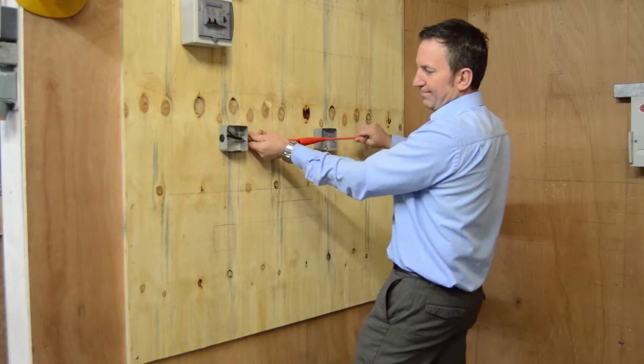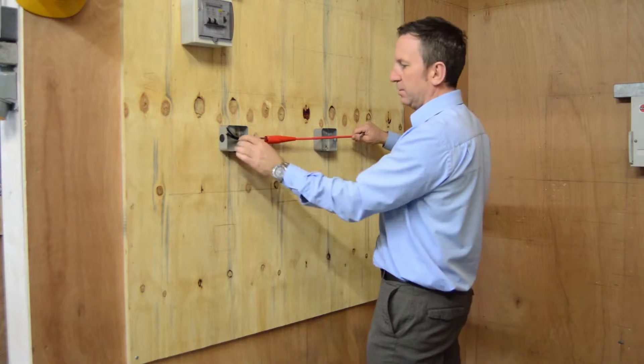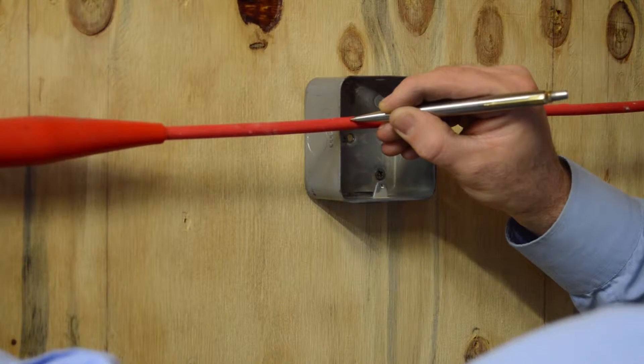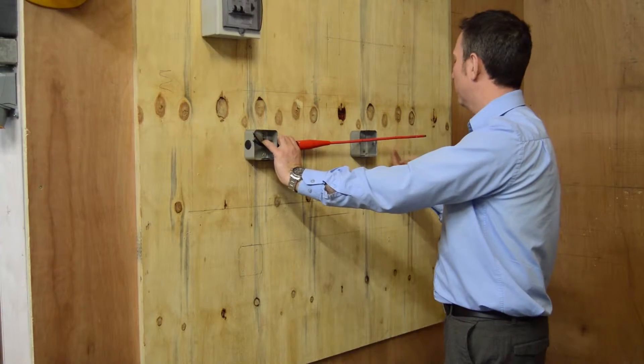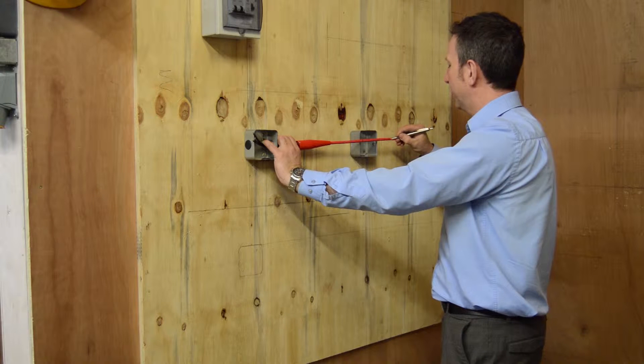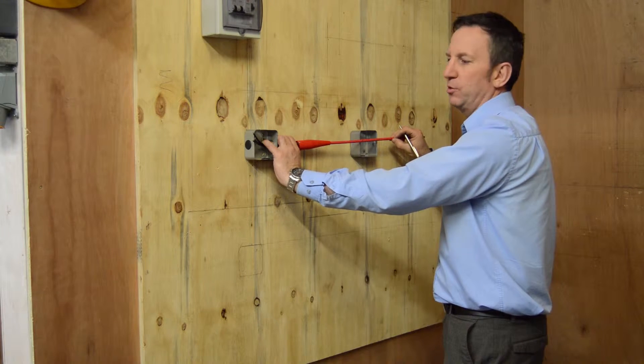In it goes in the side. We then have a look at that cable. Make sure it's pulled fully back, and we look at where the cable touches the outer side of the accessory. We're going to cut this cable to length, so make sure you add at least two or three fingers, and put our final mark where we're going to cut it to length.